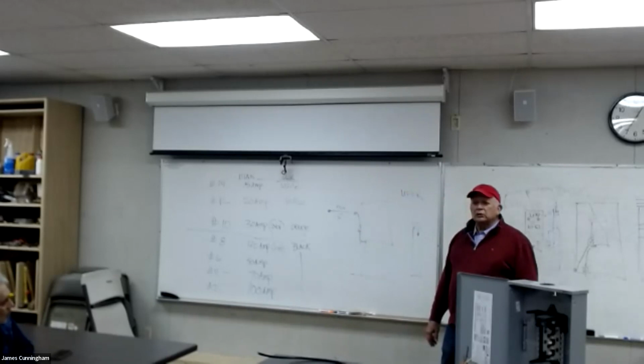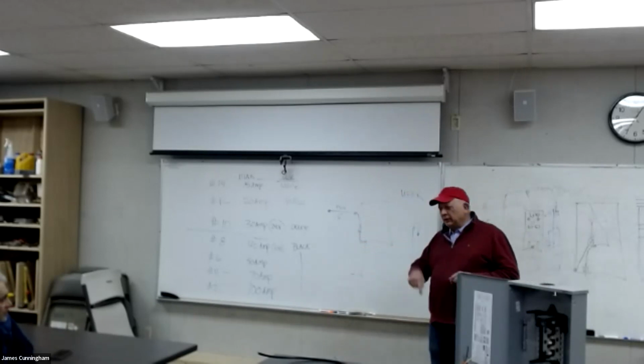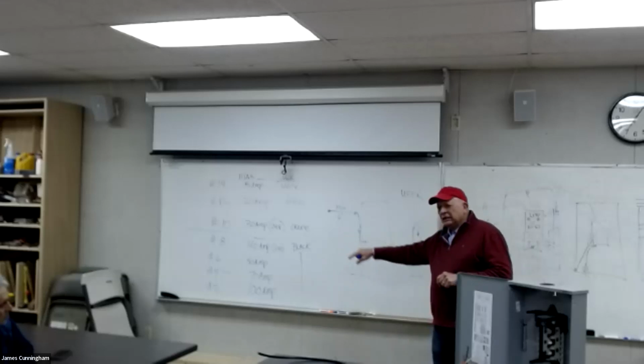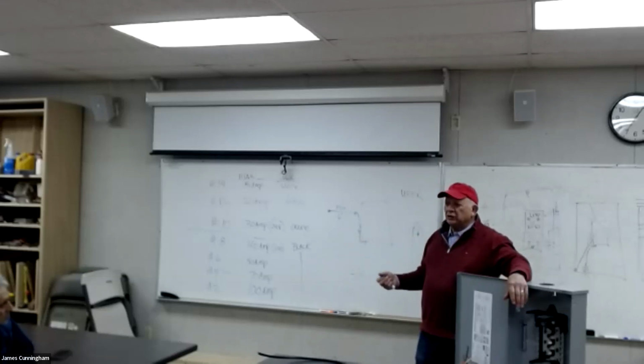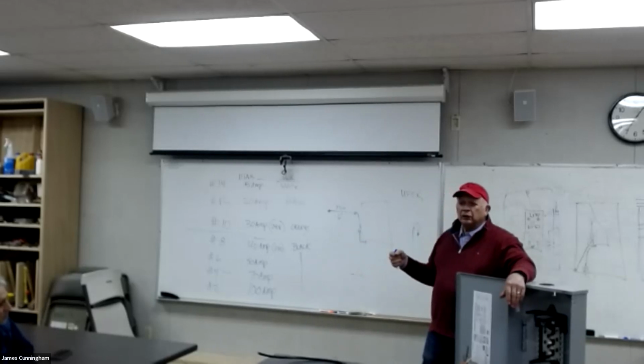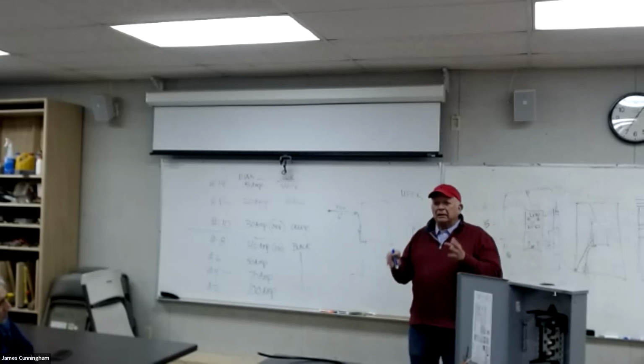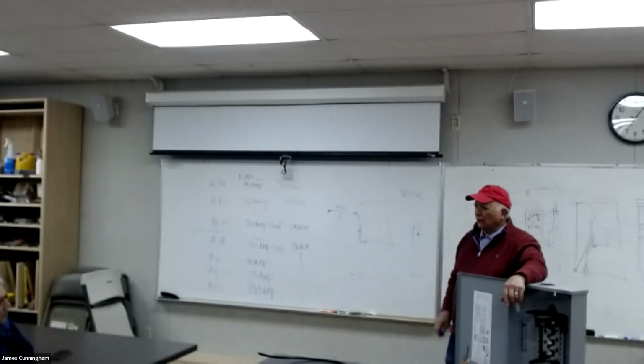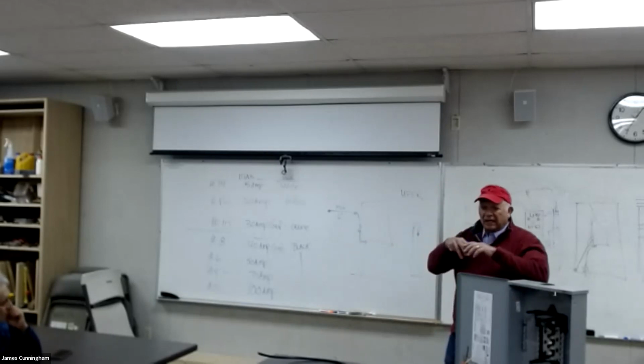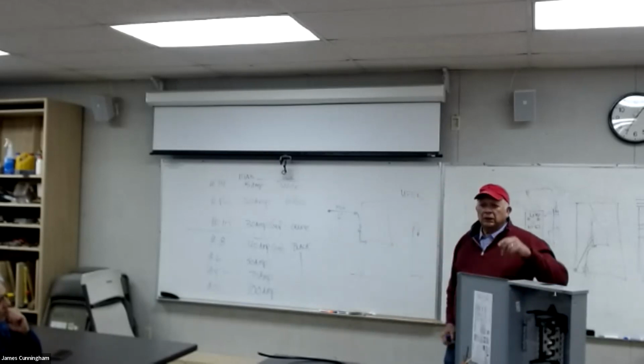We'll try to put it as close to where the electrical panel is going to be. The other part of the code says that that piece of rebar has to be at least 20 feet long. Lowest bar, at least 20 feet long. It doesn't have to be a solid bar 20 feet, it just has to be in a loop or something that's 20 feet. Then you attach it with a grounding clamp, and you bring it out of the concrete pretty close to the framing bay where the panel is going to be. That way it's already in the wall, and when you're putting your bottom plate down, you just drill a hole for it.